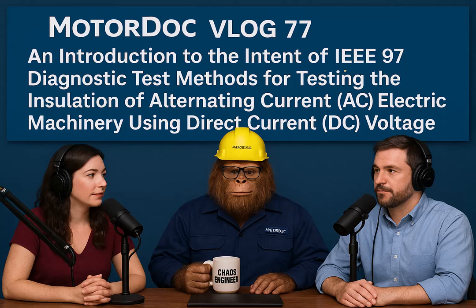Okay. What about parameters from the depolarization current? Since that part isolates the internal response, those numbers sound like they could be really powerful. They really are. The normalized depolarization resistance, RC-depol, is typically calculated at 1 minute from the start of the depolarization current. This one is independent of that direct conduction current. That's the key difference. Yes, so RC-depol is highly sensitive to the intrinsic state of the insulation: the material type, how well it's cured, its temperature, and also, to a lesser extent, the test voltage, especially as it ages. The guide really highlights RC-depol as being extremely useful for trending the internal aging of the insulation material itself, separate from surface effects.